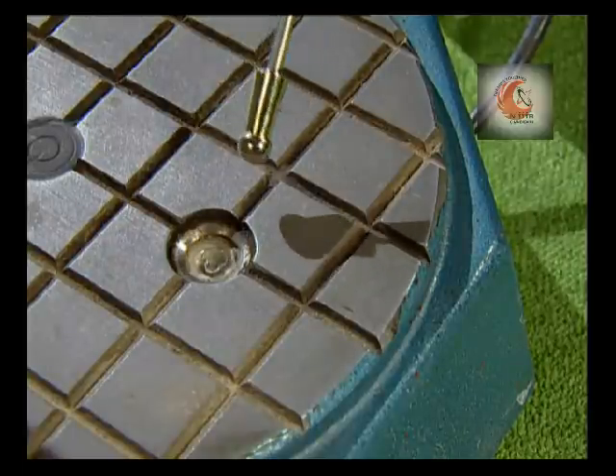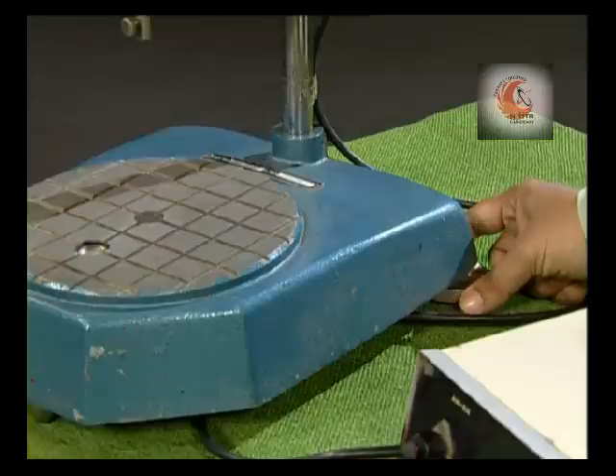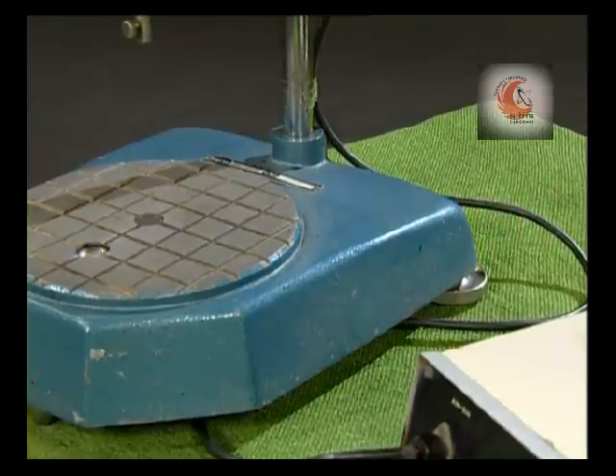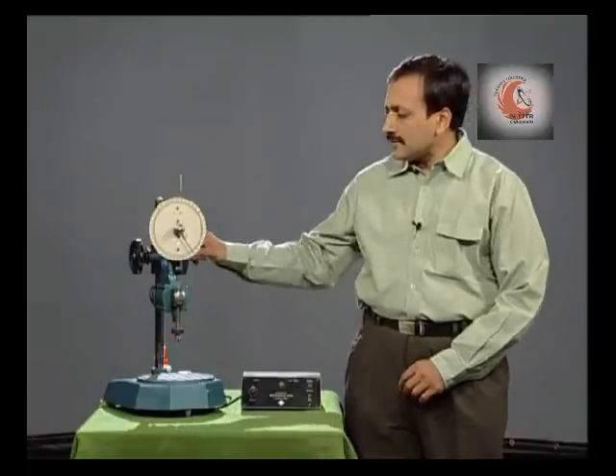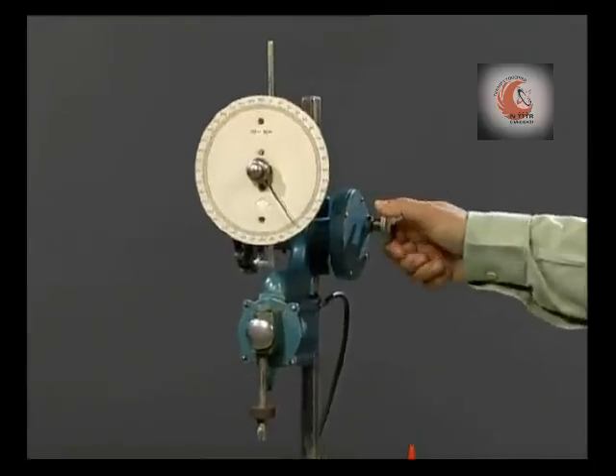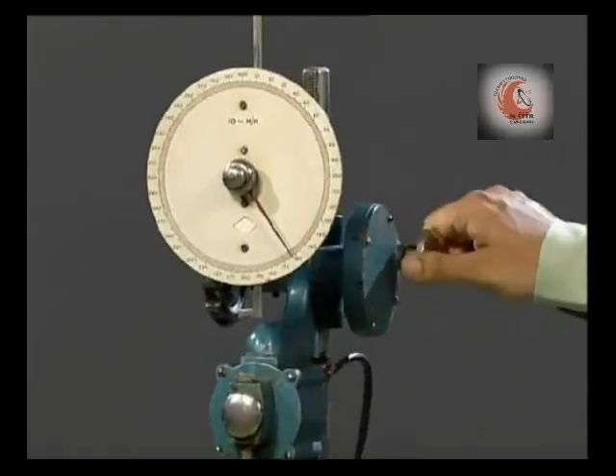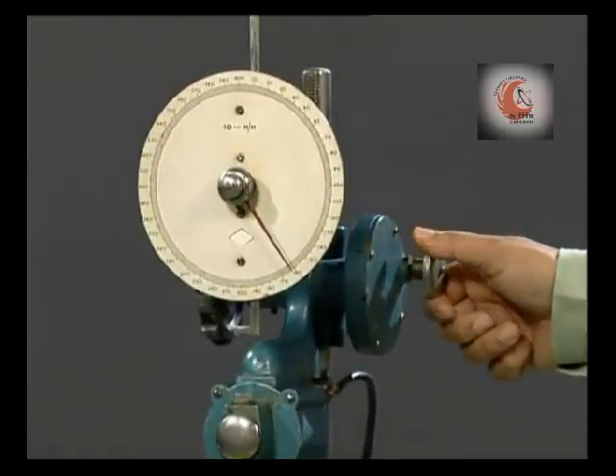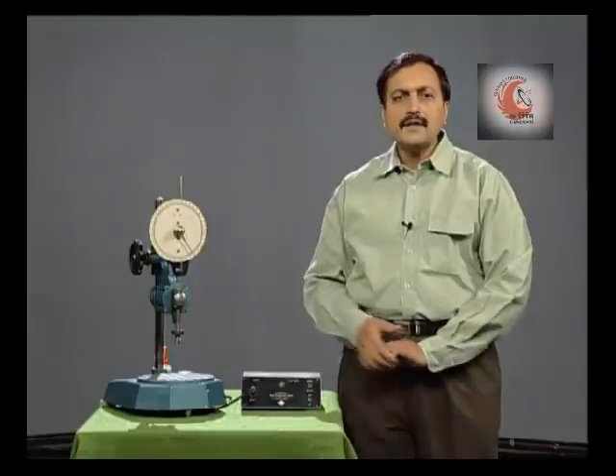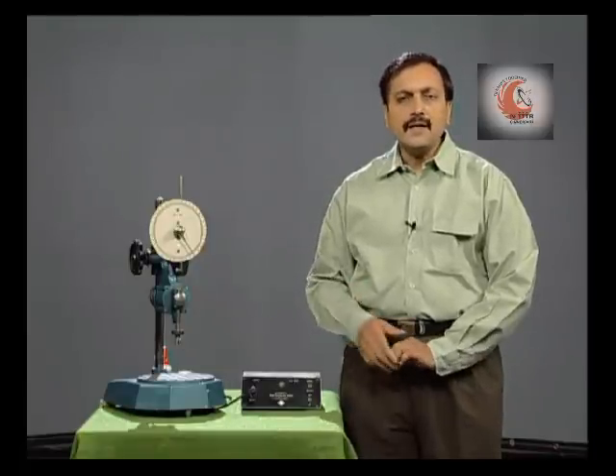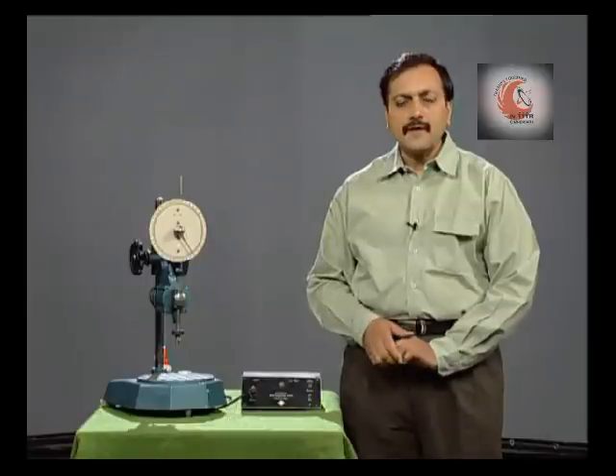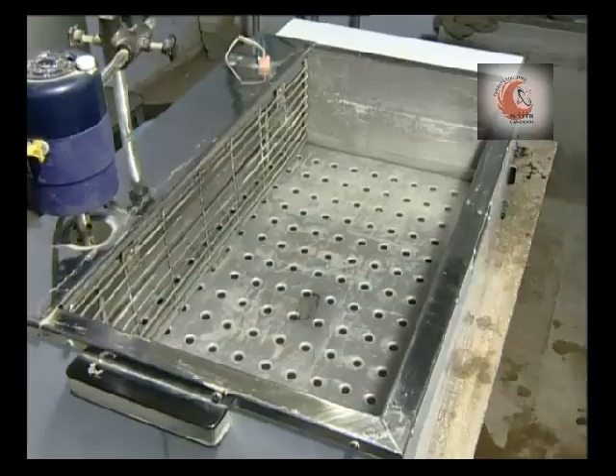It has a spirit level at the base to ensure proper leveling. The instrument also has finer control for vertical movement of the total assembly. This enables the needle to be perfectly in touch with the bitumen surface while carrying out the test. We also need a water bath that can be maintained at 25 degrees centigrade.